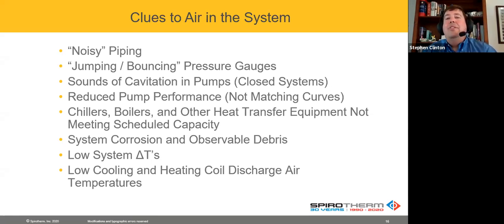But we have a lot of case studies that have shown that after removing air from the system, primarily in the dirt too, you see the system operating the way that it's supposed to. We see that too in low system delta T's. How many times do you have a project? You're designing a new one, you have an existing one, you're trying to get a project started, it's not working. Well, what do you do? Well, think about that. If you're looking at energy and my fluid's not the right fluid, something has to give somewhere.